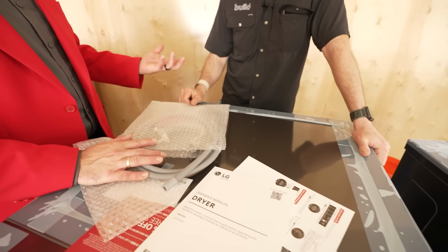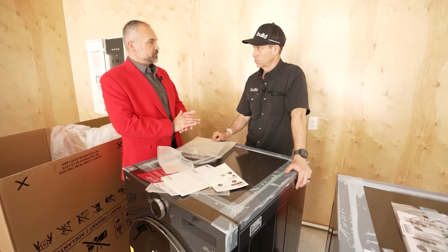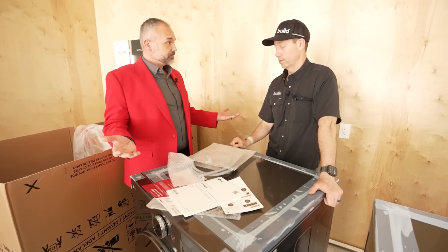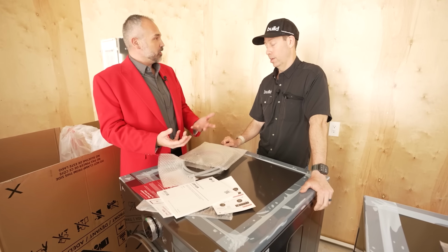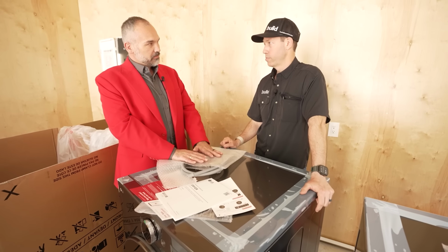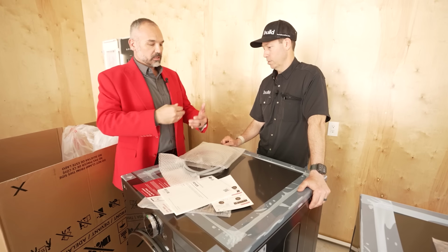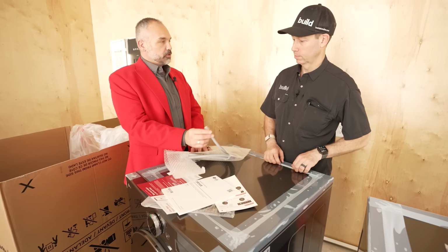In a typical situation, let's talk a typical electric or gas dryer, you're going to have about 200 CFM of air being exhausted outside, dumping outside, right? And you have a tight house. How many of us think to provide makeup air for a dryer in a tight house? We think about it for a kitchen exhaust hood, for sure, but we don't think about the dryer. This is a 200 CFM exhaust that's now taking our conditioned air, drying the clothes and dumping that conditioned air with the moisture outside. That's right. This thing instead recycles that, condenses that moisture, and we dump it through the condensate tube.